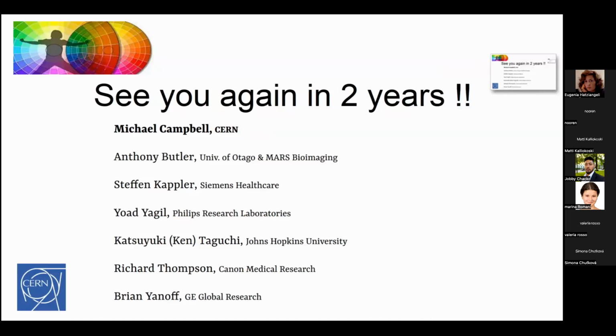So one thing that's really clear is big manufacturers are bringing in machines at the top end of the market, you know, a few $1 million a machine. And I think that's going to be really challenging because most health systems actually can't afford the systems they've got already. But I think the technology is more of an enabler. So photon counting works really well at low flux, low X-ray power. So in our scanners, we have a $10,000 X-ray tube. In a traditional CT scanner, you have a $200,000 X-ray tube. The Siemens guys told us yesterday their photon counting system for speed has 2 X-ray tubes at right angles. So just in your source, you've got 400,000.